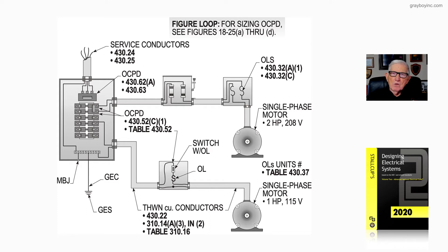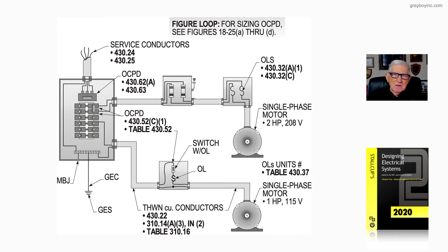Section 430.6A states these are the full-load currents that size every element of the motor circuit, except the overload protection, which uses the nameplate, and 430.6A2, which we will look at later. Based upon that information, let's look at Figure 18-1 in Chapter 18 of Stalkup's Electrical Design Book, Volume 2.